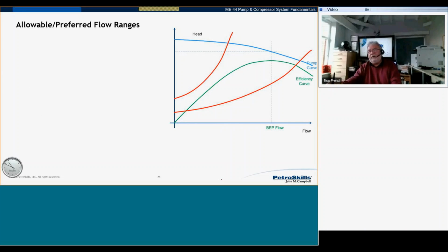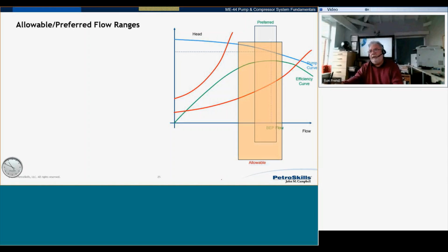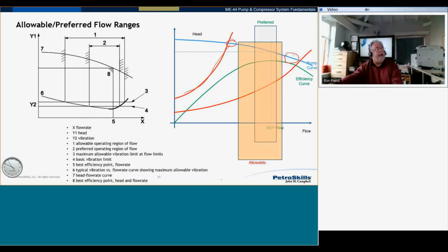So one thing I want to remind you guys about is you've got 2 ranges in your pumps when you get your data sheets. You've got your preferred operating range and you've got your allowable operating range. Make sure when you do your sensitivity analysis that your pump is not operating outside of those ranges. And the way I've drawn this sensitivity analysis here, that thing over there, I'm outside the allowable range. Over there, I'm outside the allowable range. I would much rather stay within the preferred operating range. But if you operate out there, you are going to get a lot of failures.